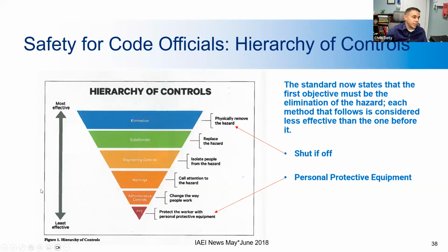If you can completely shut the system down while you're inspecting it, if you have to get into any of the electrical components, that's definitely the best way to do it. But many municipalities have gone to visual inspections only, with no opening of junction boxes or electrical panels, and this is why: to completely remove the hazard. It prevents people from having to be exposed to the hazards. And this is another reason why photos are required during the installation, because it allows you to see inside some of these things while they're being installed and before they're energized, which reduces the risk to inspectors who are typically not licensed electricians. So that's the hierarchy of controls and how that's used.